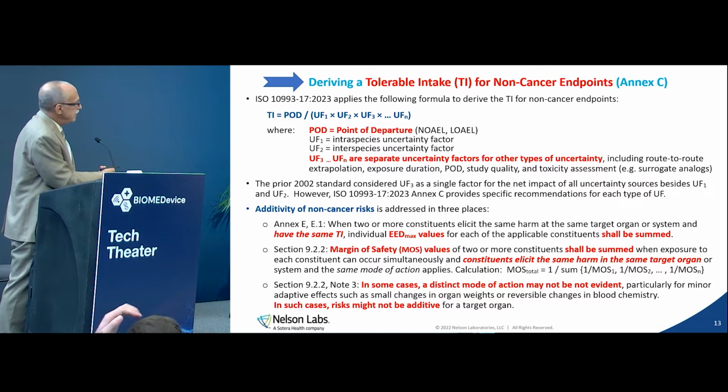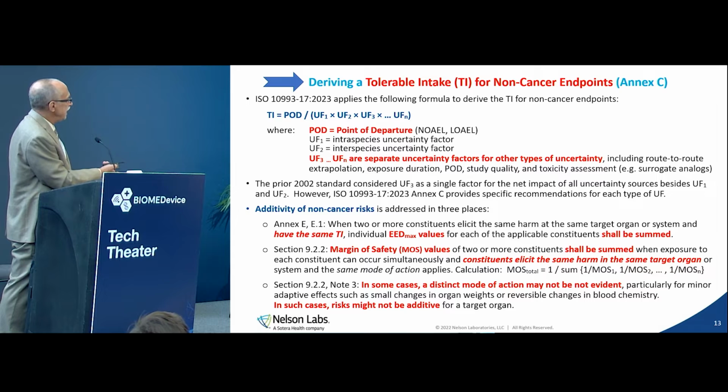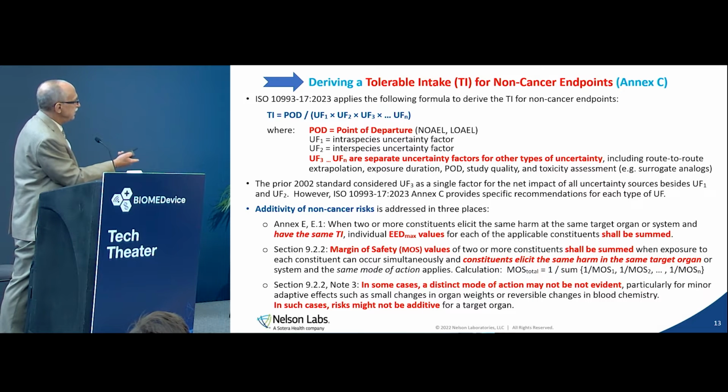Lastly, additivity is a new concept in here in 3 different places. When 2 or more constituents elicit the same harm at the same target organ or system and have the same tolerable intake, we must sum the estimated exposures for each constituent.